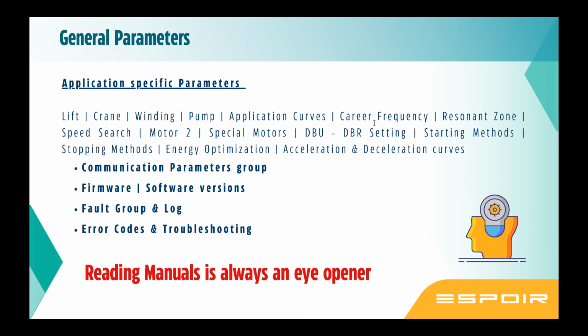For example, you have an 11 kilowatt drive. You have two motors to run, two pumps. At peak load, you run a 10 HP pump, and at low peak, you run only a 3 HP pump. So now you don't have to buy two VFDs to run that. You can use the same VFD, set motor 2 parameters in it, and select a logic by which you can choose motor 2 when you are going to run the 3 HP motor. That parameter it will catch and run. So here you can intelligently use your resources.